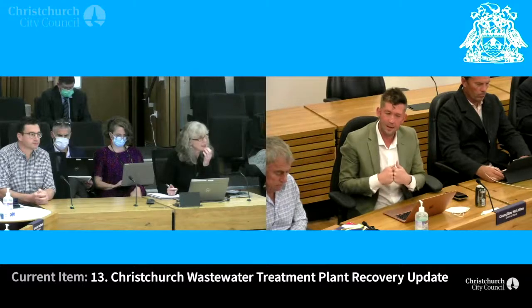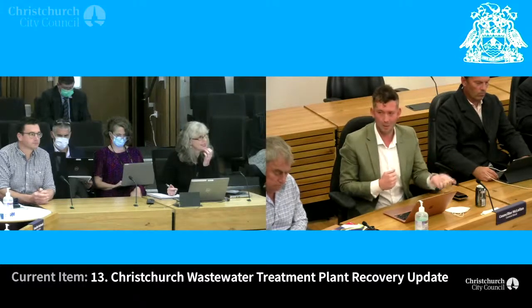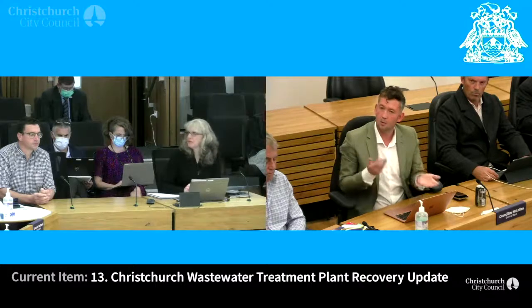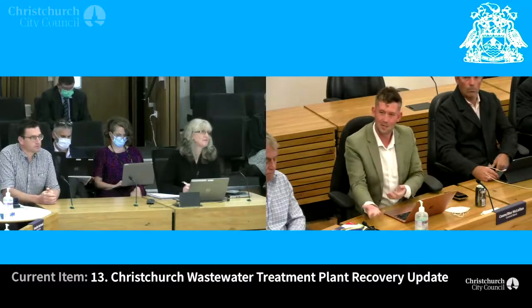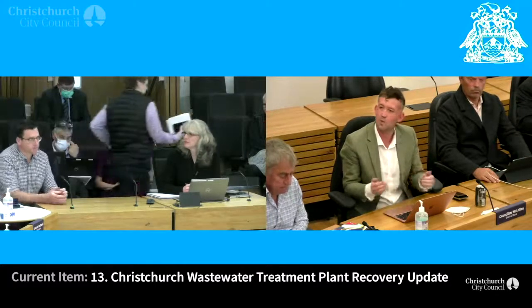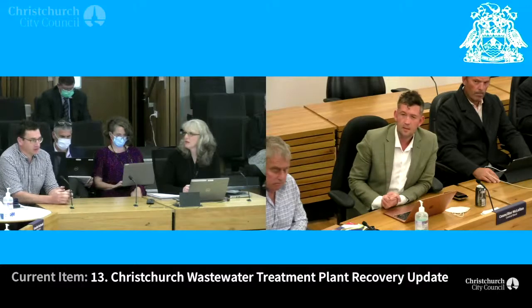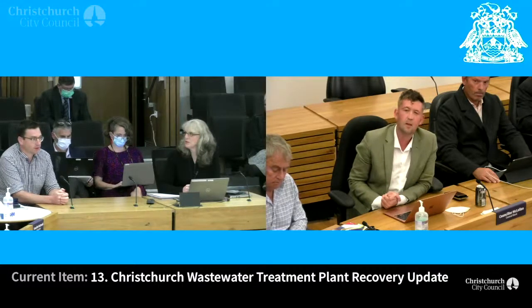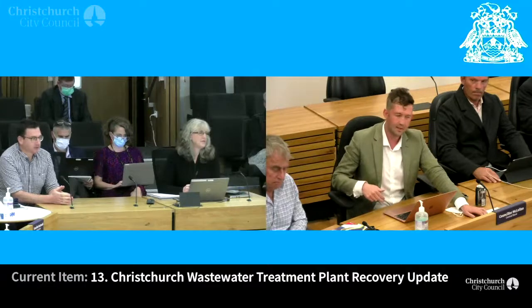Just clarifying — when we realised the really bad source of odour was the media in March, it was within a month that we got the go-ahead to proceed to remove it. Given that the media obviously smelt incredibly bad immediately after the fire, was it assumed the smell would simply go away? The initial smell after the fire from the trickling filters was burnt plastic media which dissipated over time, and with it being dry it didn't smell for a couple of months — so it's a different odour from the same source essentially.